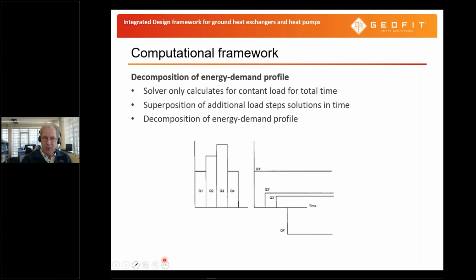So the first thing is to take a look at the decomposition. If we have here an energy demand for 1 month, 2 months. In this month, we have a certain heat load. In the second month, we have a higher heat load. In the third month, an even higher one. And then in the fourth month, a lower one. We have to calculate the first time step for the whole duration of the simulation. So we calculate this load here. And then we say, okay, in the second month, we have a higher load. So the difference between these two, we calculate, and then we add it to the effect of the first one, starting in month 2. For month 3, we have still higher heating demand. So we calculate that from month 3, and we add it to the solution of month 1 and month 2 that run through the whole period. And in this way, we can calculate the exact energy profile for all the months and years that we are interested in. This is the principle of superposition of a decomposed energy demand profile.